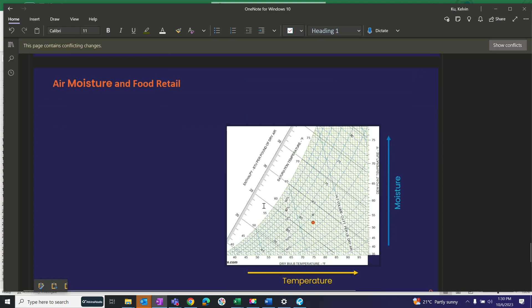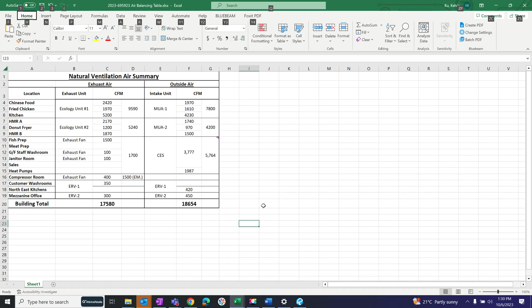So that capacity matters. But to a refrigeration equipment, its coil is at a fixed temperature. Your freezers are sitting at minus 30 Fahrenheit or whatever the case is. They don't care about the capacity of the air to hold moisture. All they care about is at what temperature is that moisture going to condense and freeze on that coil. And so we always use absolute humidity, not relative humidity. I was looking for somebody to stop me there, because that is what matters to the equipment. And so we use different measures for that.